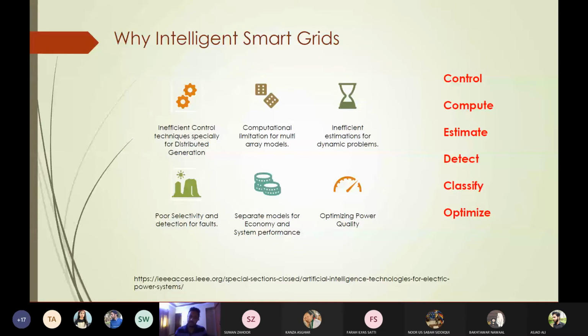Another reason we need smart grids is inefficient estimation in dynamic problems, because system dynamics are a key characteristic of the system. We are moving towards low inertia systems, since generators and dynamos are obsoleting themselves, and we're moving towards inverter-based systems including wind turbines, solar panels, and other renewables. So system dynamics become a problem, because you won't be able to detect a frequency surge since there's no mechanical rotor attached back to any generator — because there is no generator.